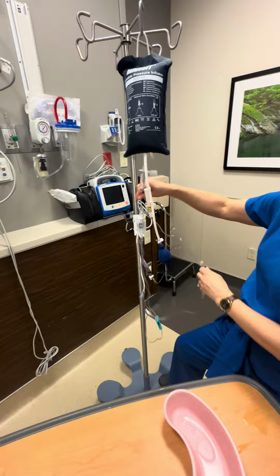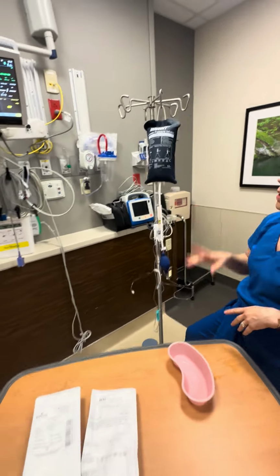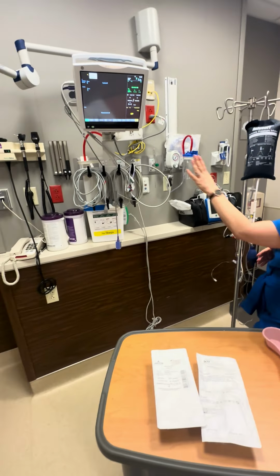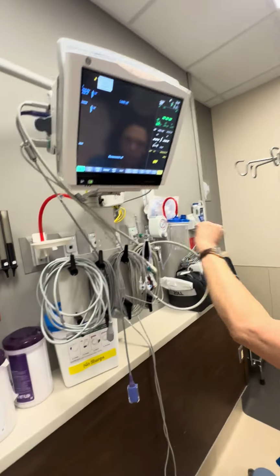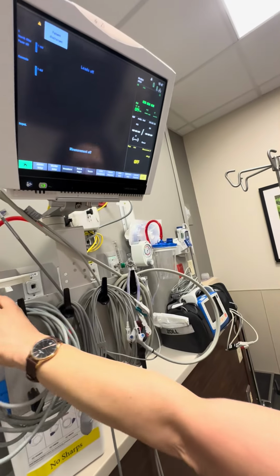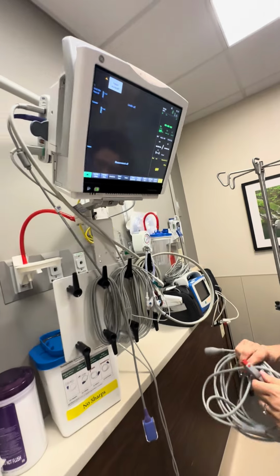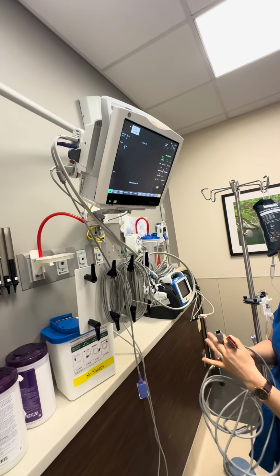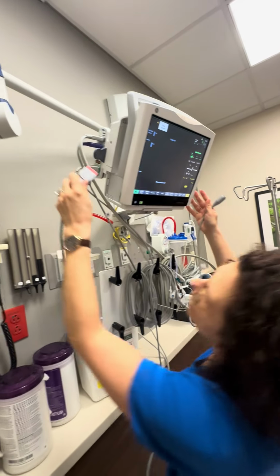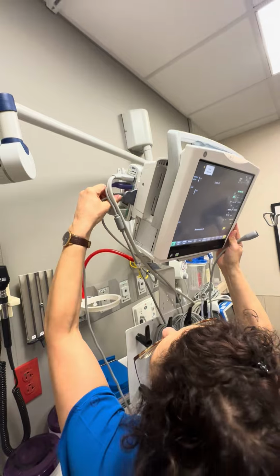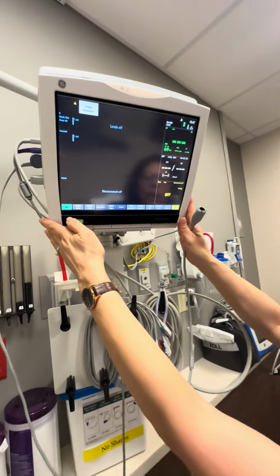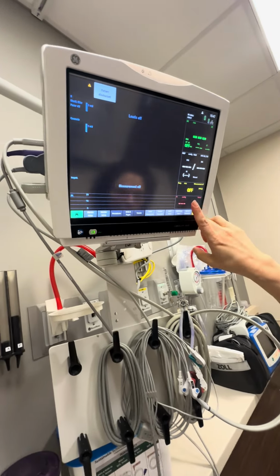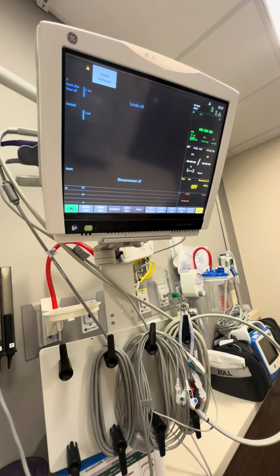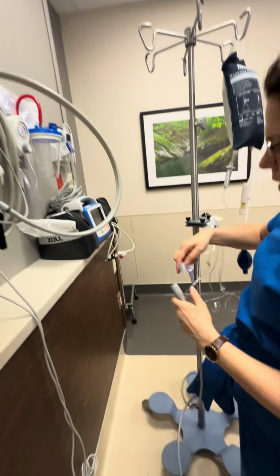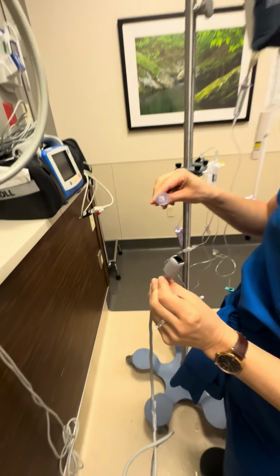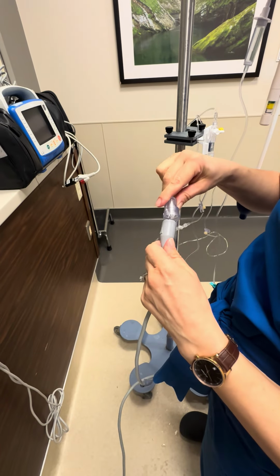Once you have that primed and ready to go, we're going to set it up to our monitor. So you're going to see the monitor isn't showing any art line measurements at that point. It won't until you plug in the cord. It's going to be the red line with the telephone jack on it. So we'll plug that in there. And then you're going to see P1 comes up. This part here attaches again onto that little tail. So you just attach the 2 pieces.